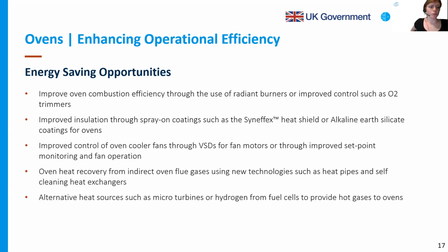Oven heat recovery, this is specifically for indirect ovens that use convection. The heat can be recovered from the flue gas using heat pipes or self-cleaning heat exchangers. Maybe a little bit more time on heat pipes. Heat pipes are devices used for heat transfer between two surfaces. Typically, heat pipes are evacuated, sealed pipes. They have a working fluid running within these pipes, and it's a two-phase operation that enables efficient transfer of heat between two locations.